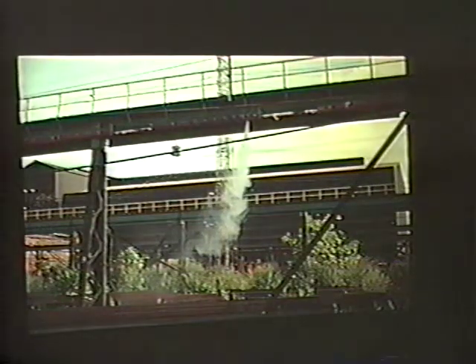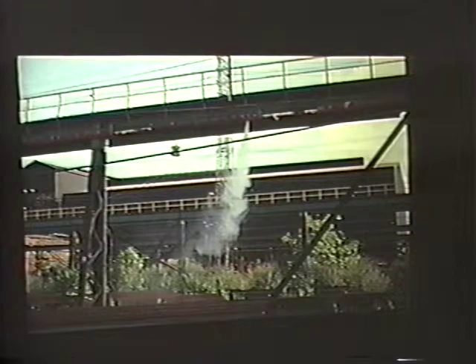The energy coordinator or your supervisor is also the person to call when you spot a steam leak. Most employees can't fix steam leaks, but there are people in the air, water, and steam group and the maintenance department who, when called, can get the leak fixed. Steam leaks are expensive. A 1/4 inch hole blowing continuously costs about $1,500 a month.